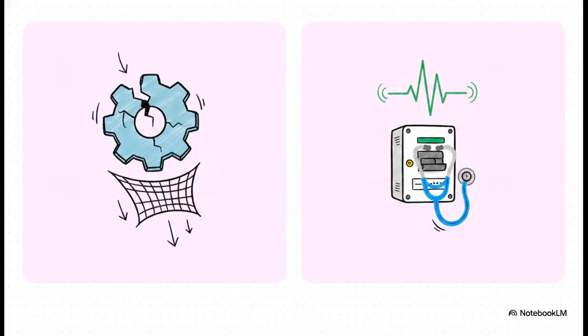If you recall our previous discussions, we looked at reactive safety nets, like breaker failure protection. Now that's your safety net, isolating faults after a primary breaker has already failed to do its job. But today, we're completely shifting our mindset. We are moving from reactive nets to proactive health tracking. The entire goal here is to catch that mechanical degradation incredibly early, effectively preventing a catastrophic failure scenario from ever happening in the first place.